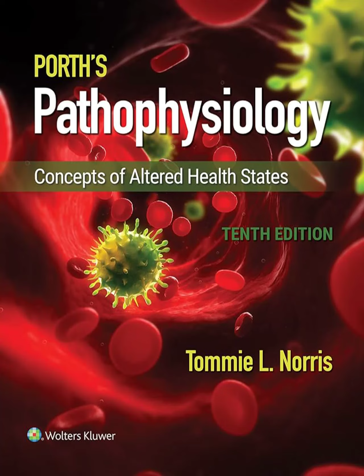One key device is the intra-aortic balloon pump, the IABP. It's a clever temporary support. How does it work? It's basically a balloon inserted into the descending aorta, just below the arteries branching off to the arms and head. It's timed with the heartbeat. It inflates during diastole when the heart is resting. Pushing blood back towards the coronaries. Exactly, improving coronary artery perfusion when the heart muscle needs it most.